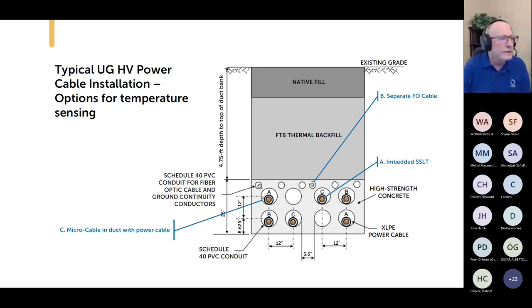Or again, if you wanted to, like I said about installing cable in a separate duct, you could do a micro cable in every duct if you wanted to. Again, some loss of accuracy, but an improvement over installing it in a separate duct and an improvement in reliability, because if for some reason optics fail, you just pull it out and put in a new one. For some reason, the power cable fails, likewise. You're not necessarily losing both in one fell swoop.